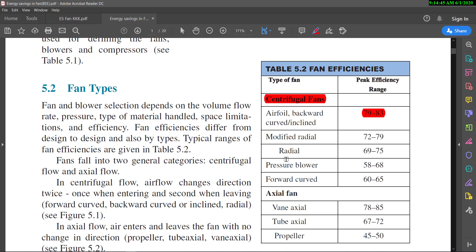Its efficiency is around 79 to 83%, as given by the Bureau of Energy Efficiency. Modified radial type fans give 72 to 79% efficiency, and radial fans provide a peak efficiency of around 69 to 75%, and a pressure blower will have 58 to 68% efficiency. Similar to backward curved, the forward curved type fans have 60 to 65% efficiency.